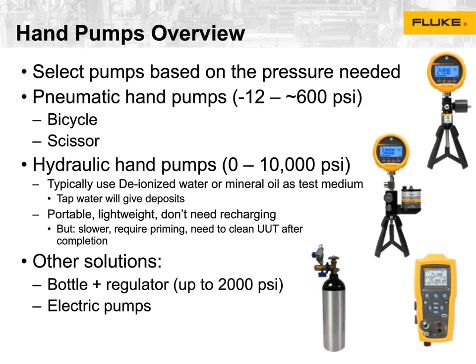One of the most common ones we see in oil and gas is because guys are taking remote trucks to either corners of the site or they are driving out to a remote field location. A lot of guys will have a nitrogen bottle in the back of their truck attached to a regulator. Works pretty well up to 2,000 psi depending on how recently your bottle's been charged, but if your bottle is low, you might not be able to generate enough pressure to do your test.